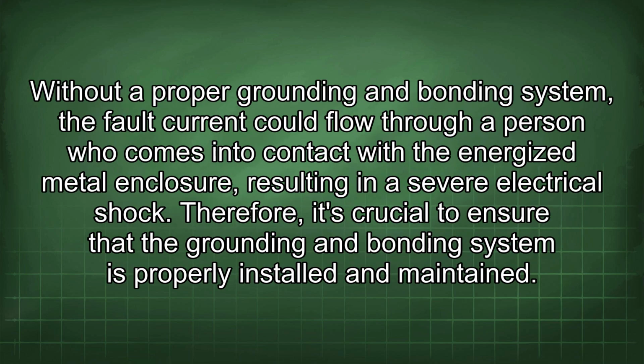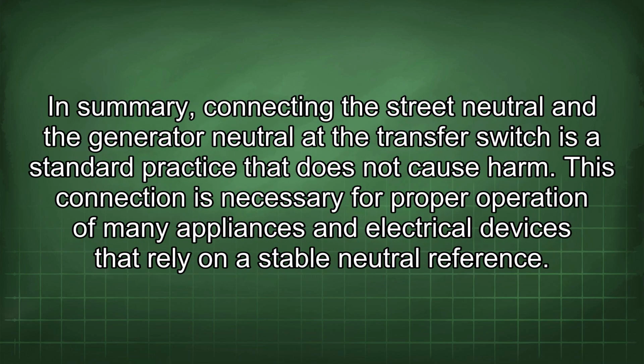Without a proper grounding and bonding system, the fault current could flow through a person who comes into contact with the energized metal enclosure, resulting in a severe electrical shock. Therefore, it's crucial to ensure that the grounding and bonding system is properly installed and maintained. In summary, connecting the street neutral and the generator neutral at the transfer switch is a standard practice that does not cause harm. This connection is necessary for proper operation of many appliances and electrical devices that rely on a stable neutral reference.